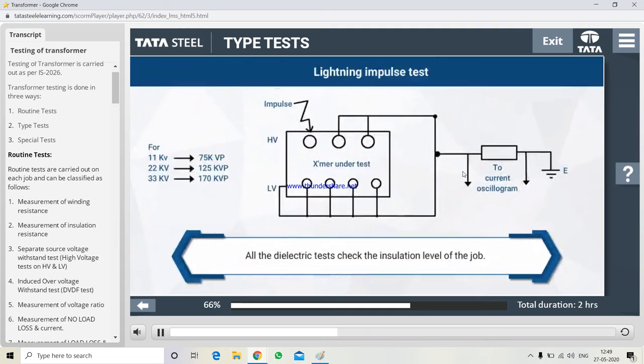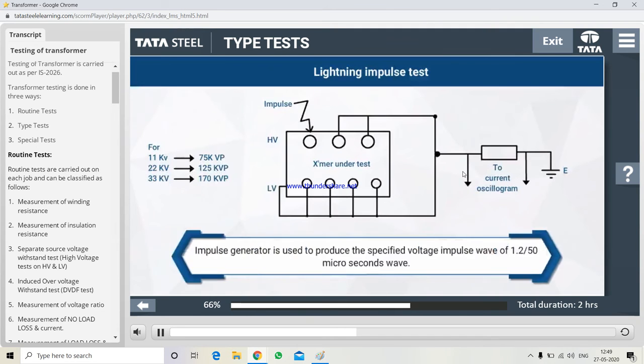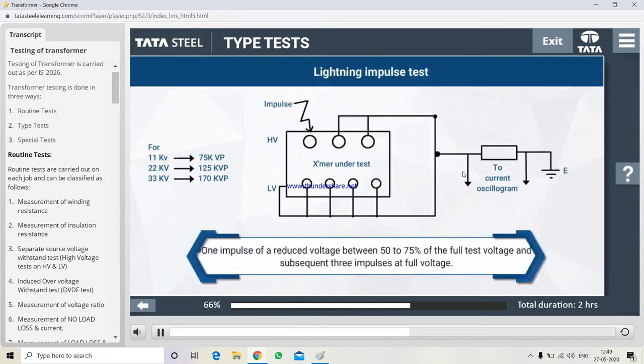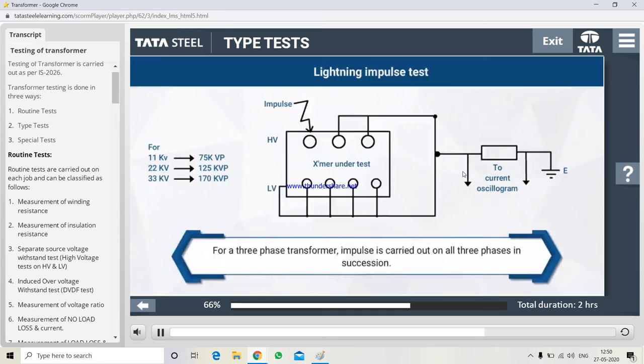All the dielectric tests check the insulation level of the job. Impulse generator is used to produce the specified voltage impulse wave of 1.2 upon 50 microseconds wave. One impulse of a reduced voltage between 50 to 75% of the full test voltage and subsequent 3 impulses at full voltage. For a 3-phase transformer, impulse is carried out on all 3 phases in succession. The voltage is applied on each of the line terminal in succession, keeping the other terminals earthed. The current and voltage wave shapes are recorded on the oscilloscope and any distortion in the wave shape is derived.